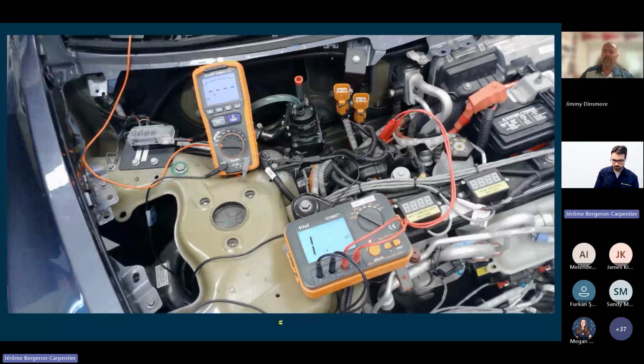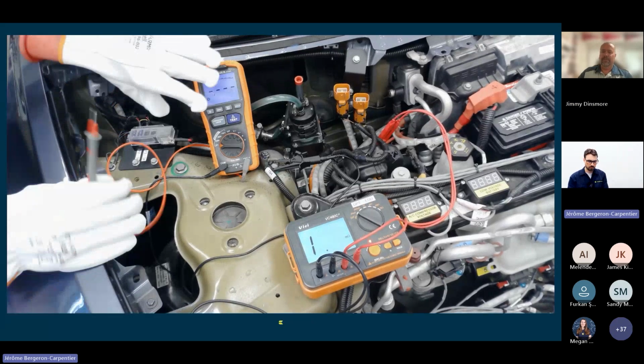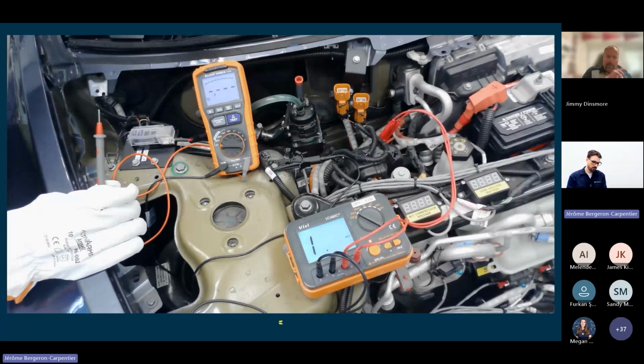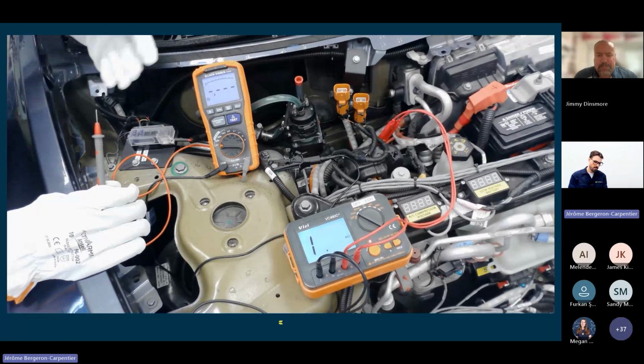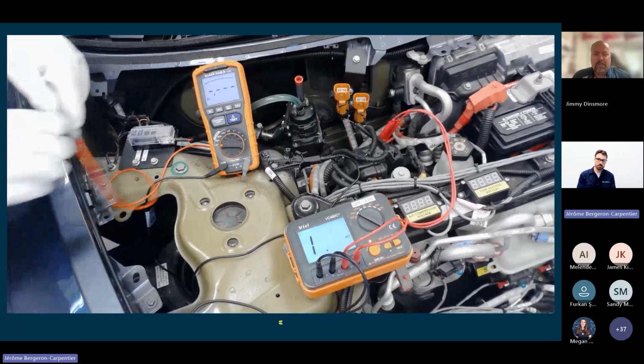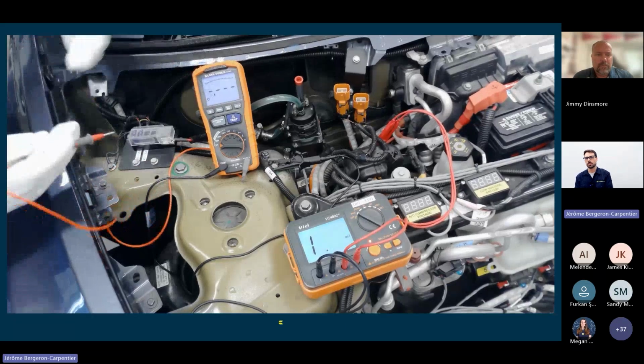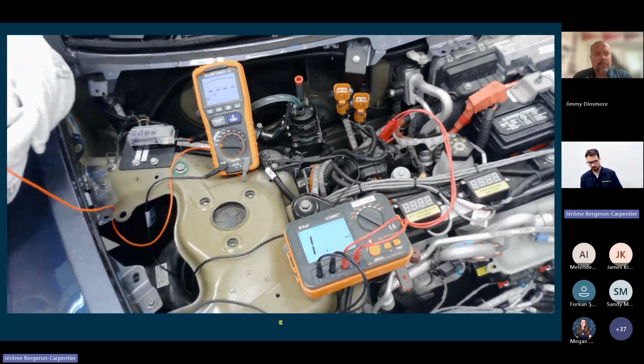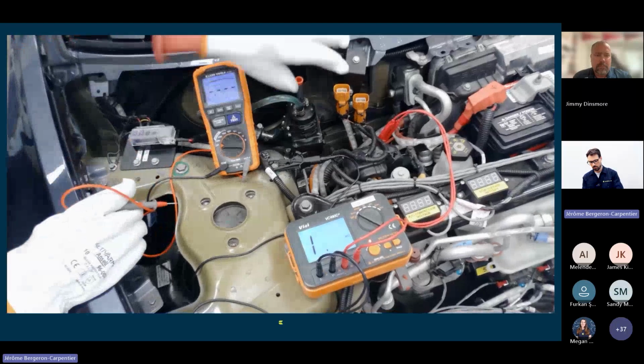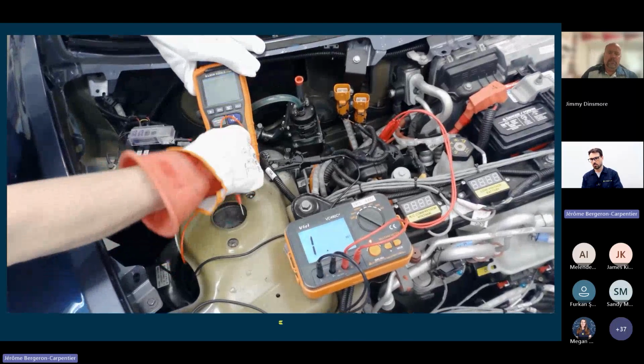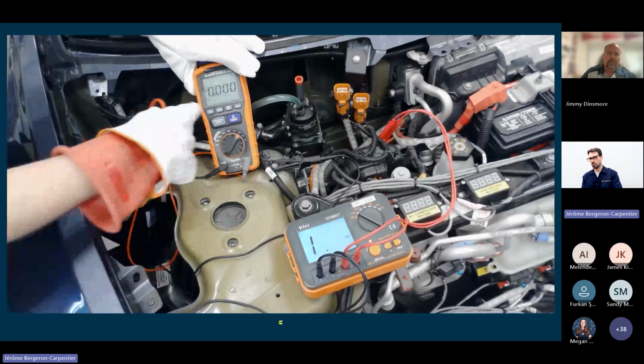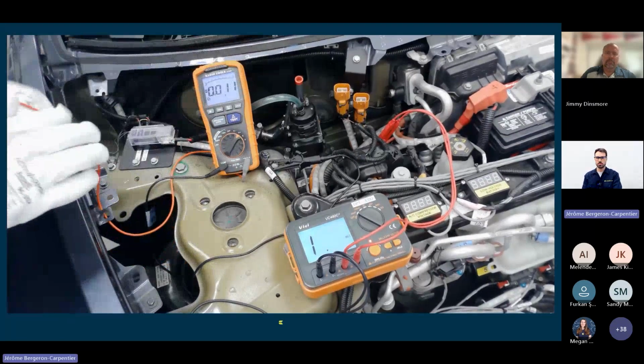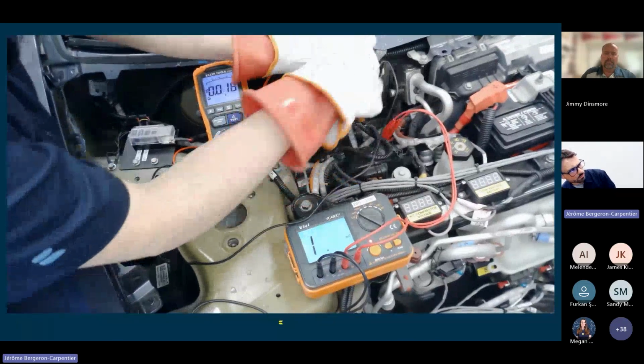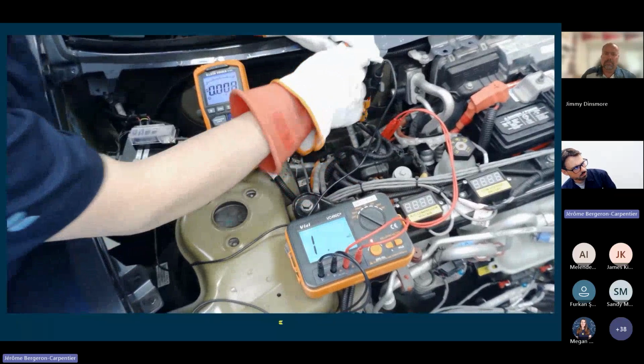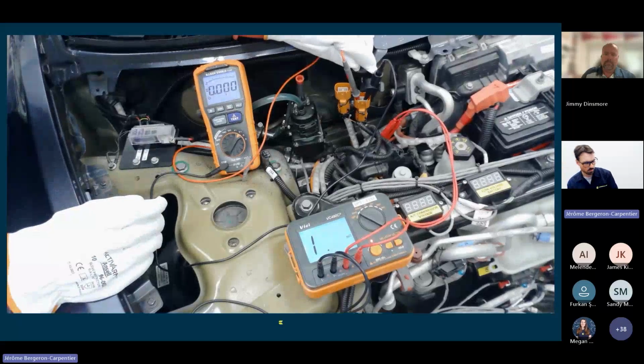Great, excellent. So what I've done is I've set this up just to emphasize the importance of testing properly, so you don't put yourself in a situation that could harm you even after doing testing. You've got to remember, there's no voltage in these components. So if I go right now to DC voltage on my meter, just to make sure, I'm going to take my meter leads, go one to one here, and touch inside here. And we can see we have no high voltage or any DC voltage there.